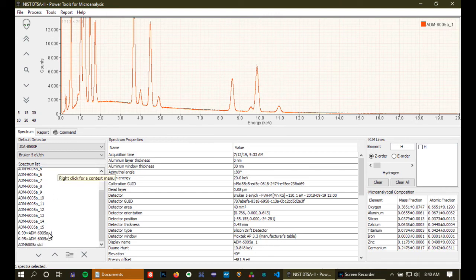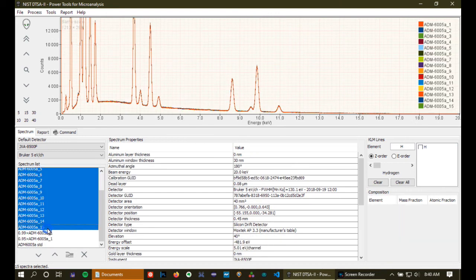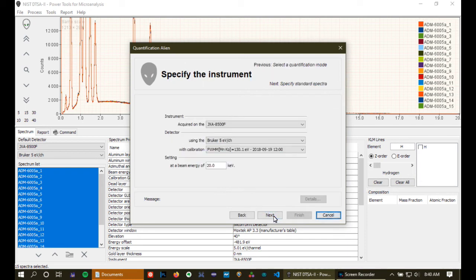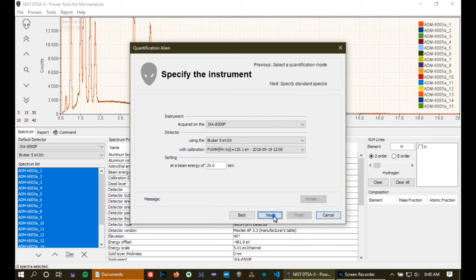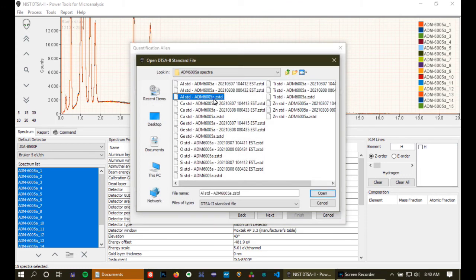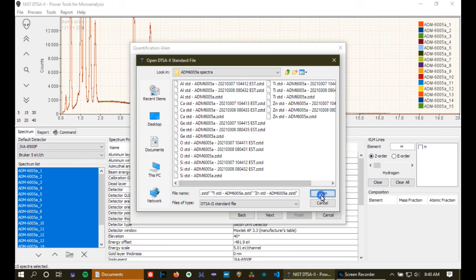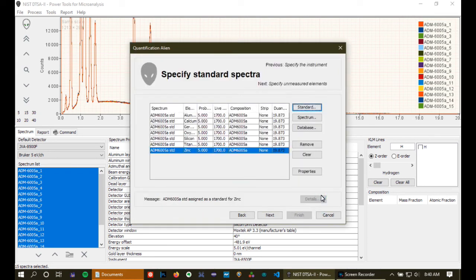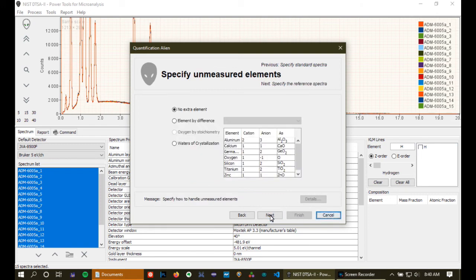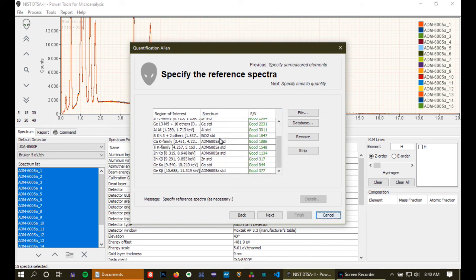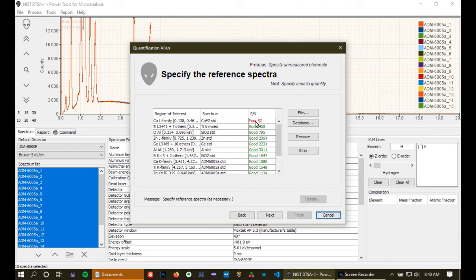Now, the last thing I'm going to do is I'm actually going to test it. I'm actually going to use these standards that I've created, standard bundles I've created to quantify the spectra that I used to create them. And I would hope that the result I get is going to be very similar to the known composition of the material. So we go to the standards. I select the standards I just created, and it looks like this. I step through. Again, because the bundle carries with it the necessary references, all of these are satisfied. I don't need to provide a reference for any of this, even though I'm using a complex standard.